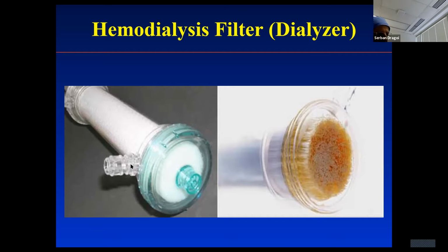So you see here, the dialysate goes into the filter below that screw-in cap, and then the dialysate circulates this way, and then the blood comes countercurrent to the dialysate from that very end in the long axis here to this one here.